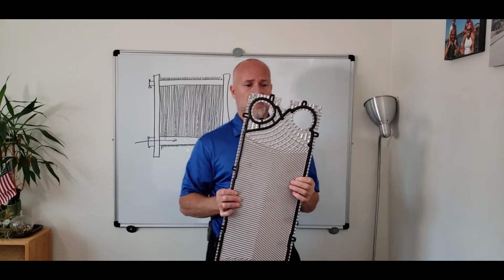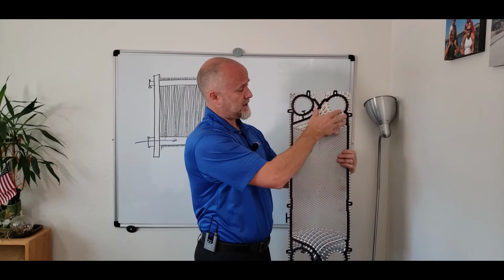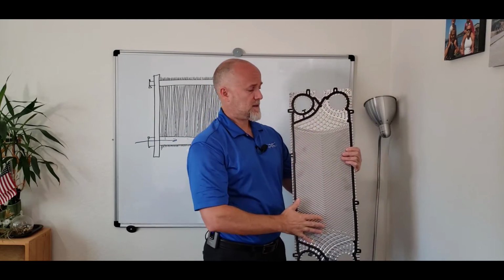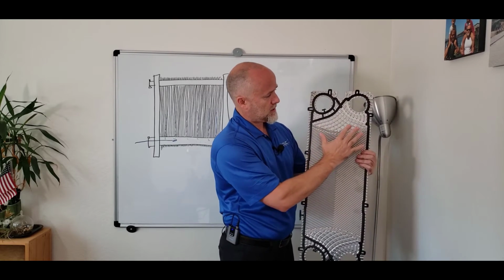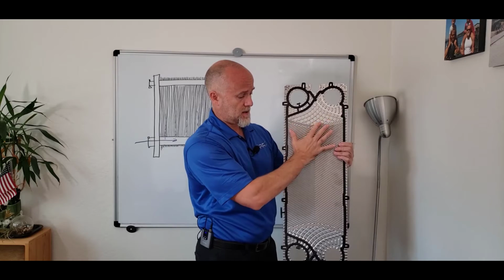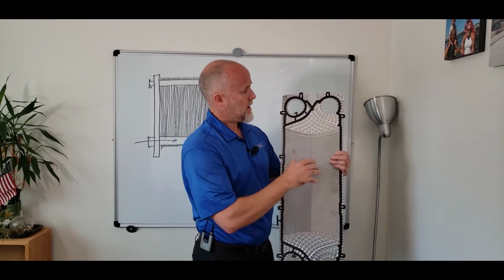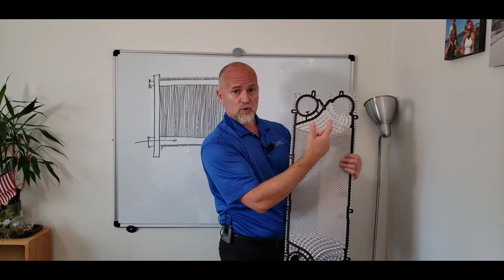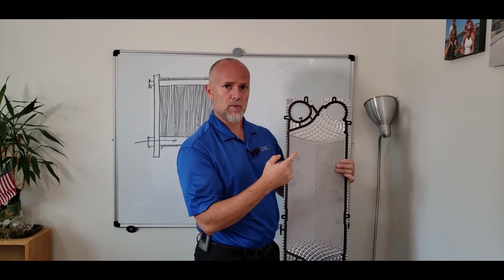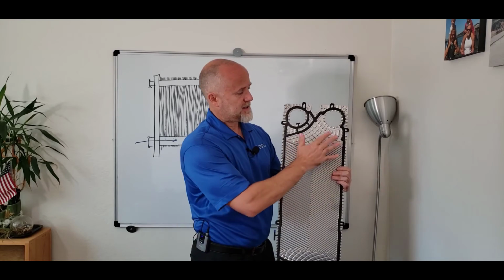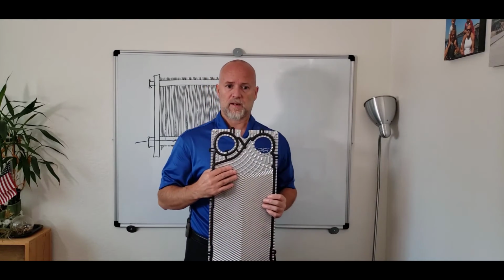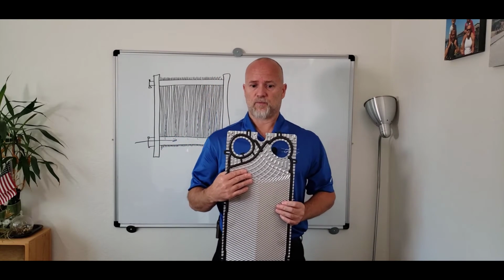And this is challenging because, as you can see, the inlet port, in this case opened by the gasket, is offset with respect to the rest of the plate. So this area, which is called the distribution area of the plate, plays a key role in making sure that you cover as much as possible of this plate with an even flow of your fluid. And a key aspect is you want to have a pressure drop of this path which is as equal as possible to the pressure drop of this path, so you don't have a path of less resistance and cold spots or hot spots that increase the chances of fouling. And this is exactly what this design does, and it has been proved that the increase in efficiency is actually significant, up to 25-30%, which is amazing if you think about that.